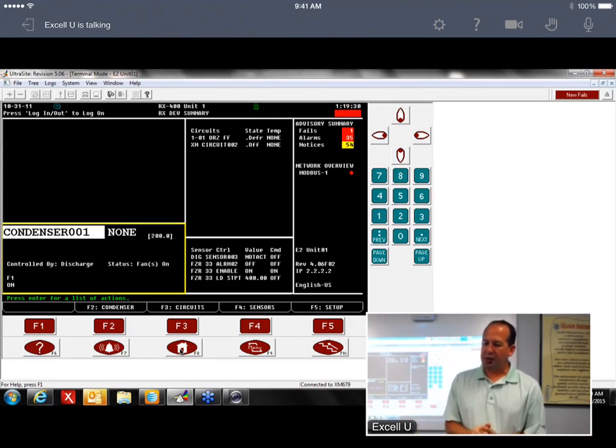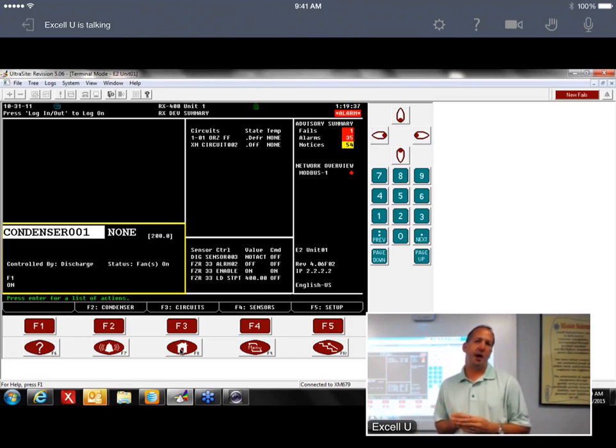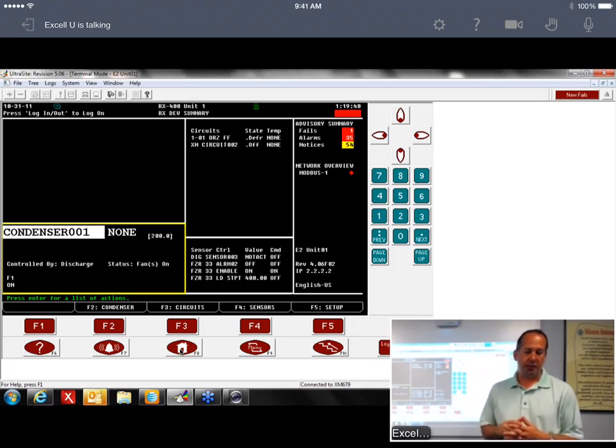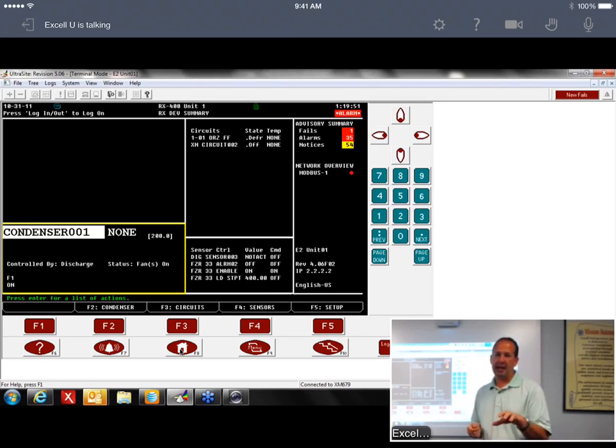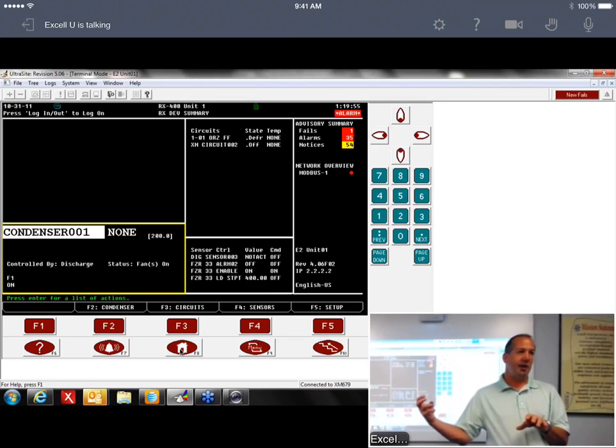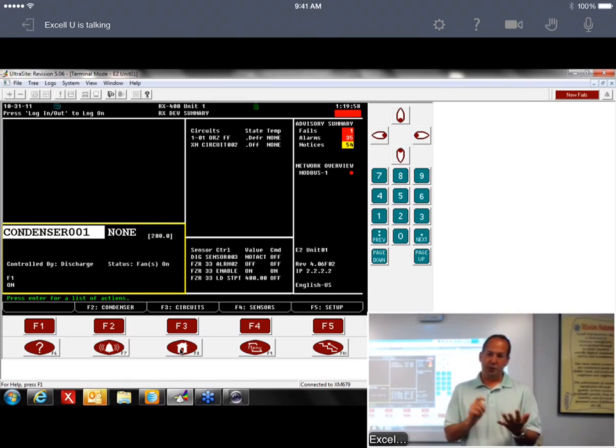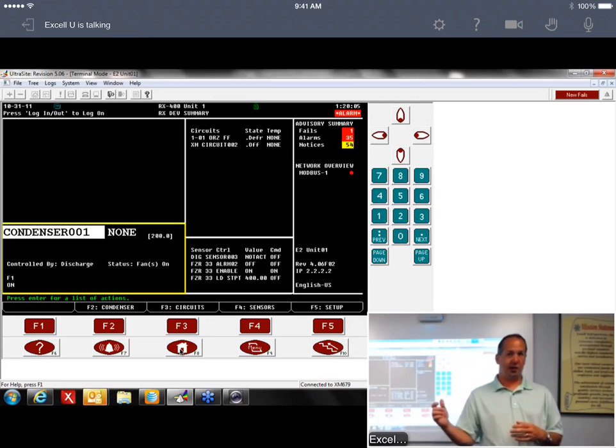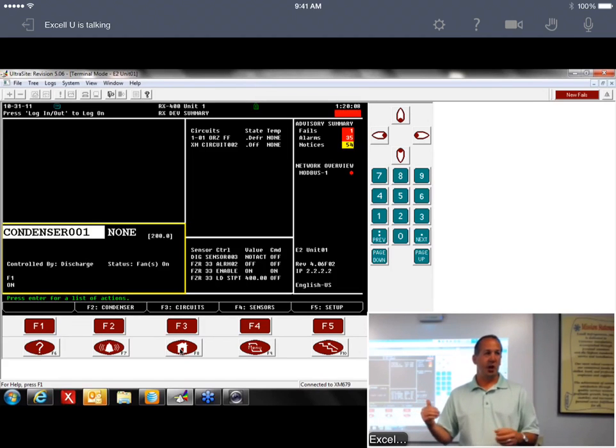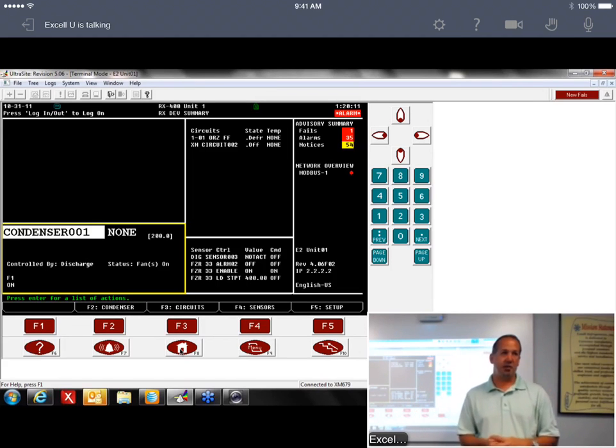So, one of the things with the way that this thing works is it's actually running two separate algorithms all the time. To control the expansion valve, it's looking at your case temp. That's its first priority, to make your case temp. And in the background, as it's controlling the case temp, it's also looking at superheat. And if your superheat gets too low, it's going to shut the valve off. I think the default setting in here is 2 degrees superheat. When it hits that low superheat alarm of 2 degrees, regardless of where the case temp is at, it's going to shut the valve off. So it's looking at both parameters at the same time. It's controlling to one, and it's got the other one going on in the background.